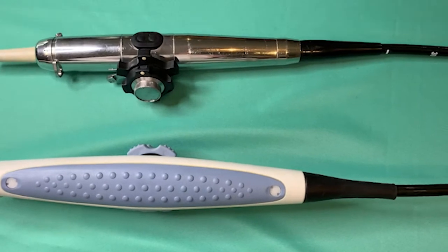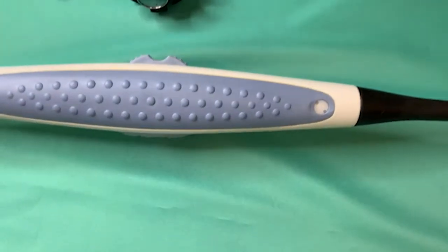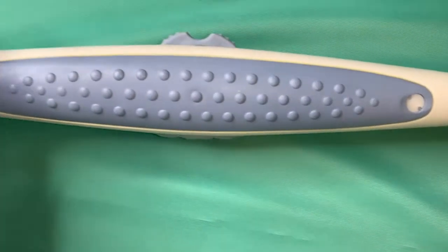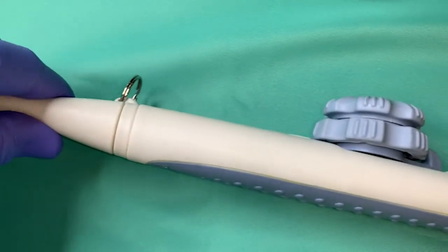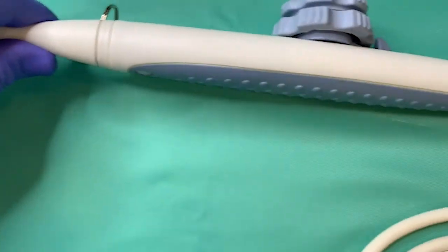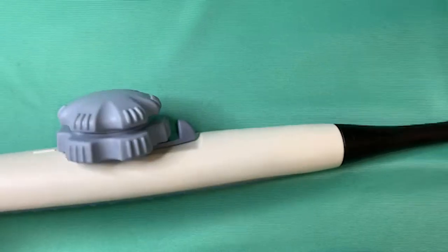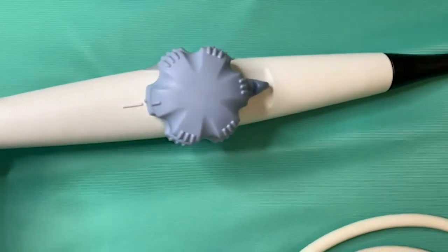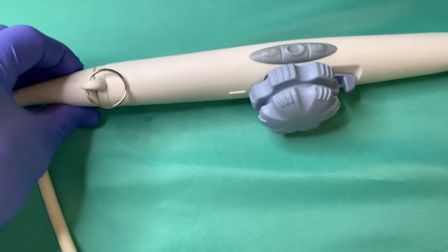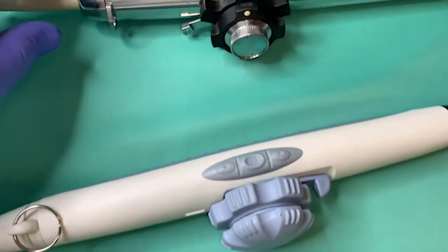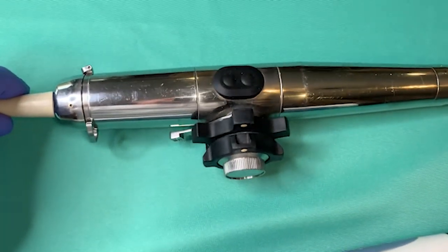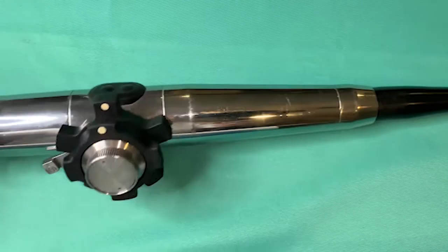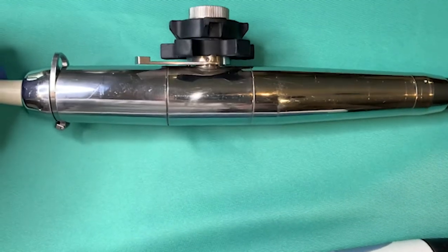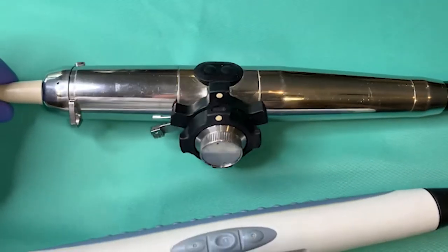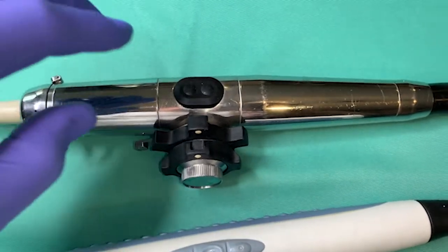The control body houses mechanical components that controls angulation similar to those in flexible scopes, but adds electromechanical components used for image orientation during patient studies. The housing is a multi-piece collection of plastic or stainless steel sections whose segments are sealed with O-rings. The area is fluid resistant, but not fluid proof. It cannot be submerged or held under running water.